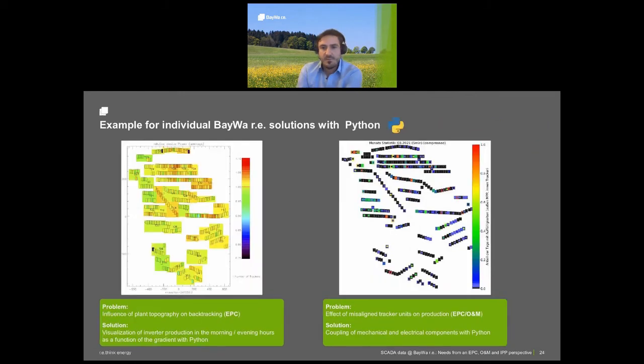Then two other ideas where we could use our internal data analysis. The problem on the left-hand side was about the influence of topography on the backtracking. Again, it's been driven by a tracker issue. So what we see here is a visualization of the inverter production in the monitoring, especially in the evening and morning hours, as a function of the gradient of the plant, done with Python. Meaning we somehow made a link between the topography, which is normally not incorporated in a standard monitoring system, and the inverter productivity in the morning and evening hours when the backtracking takes place.